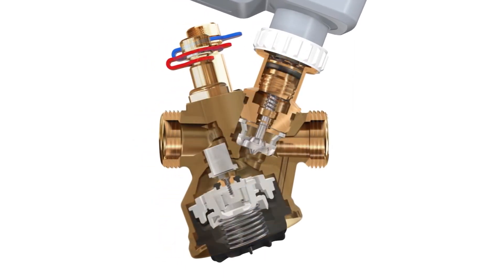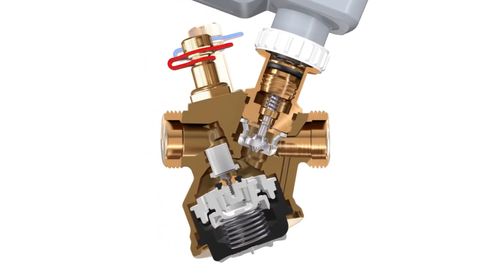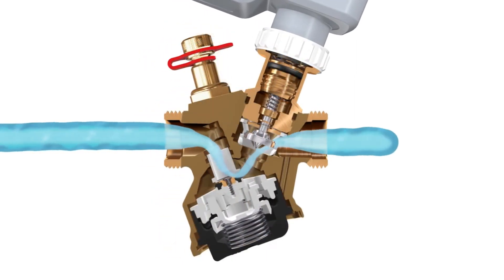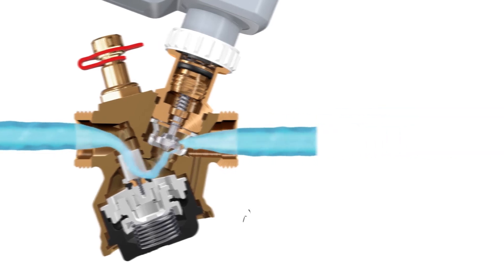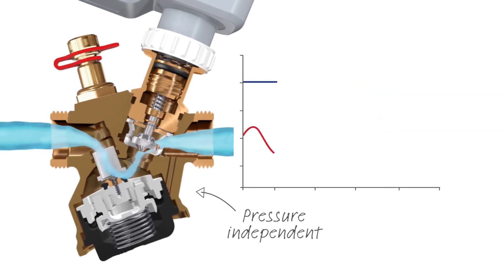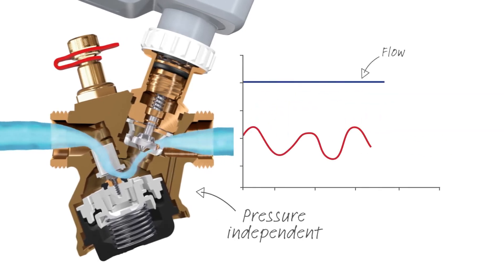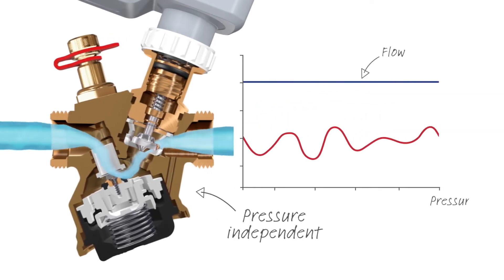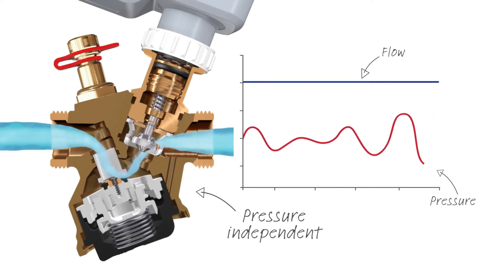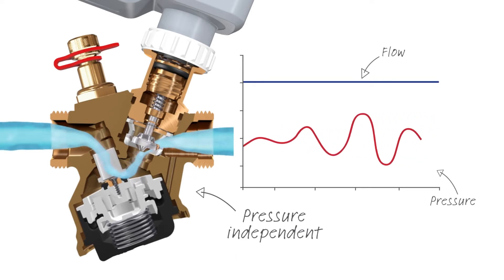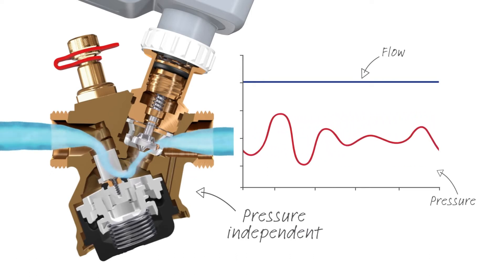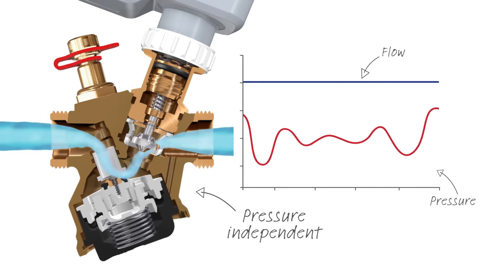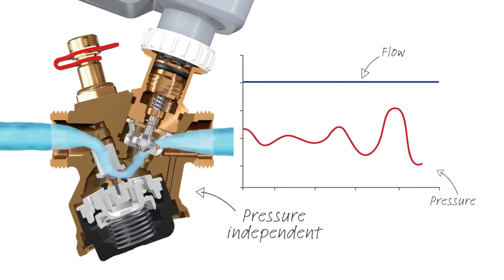The built-in pressure controller limits the maximum flow through the valve when the actuator is fully open. TA Modulator is a pressure independent valve — it keeps the flow constant regardless of pressure fluctuations in the system and guarantees high control authority.